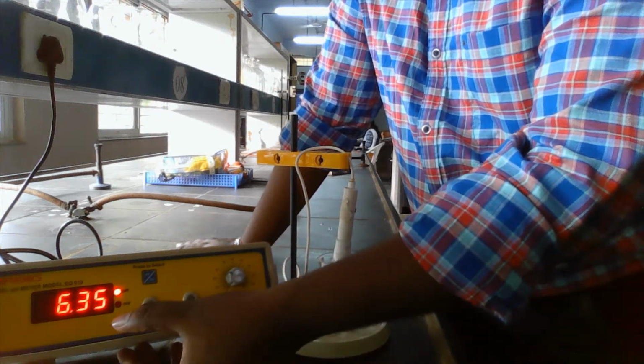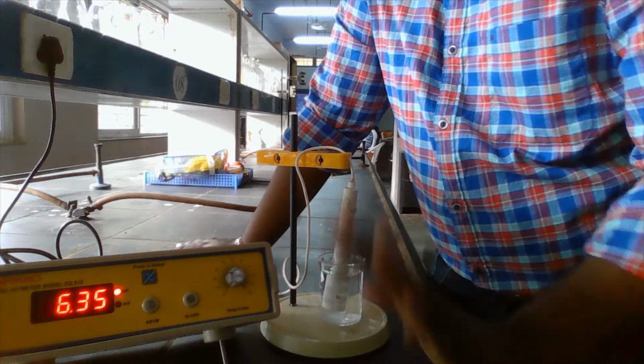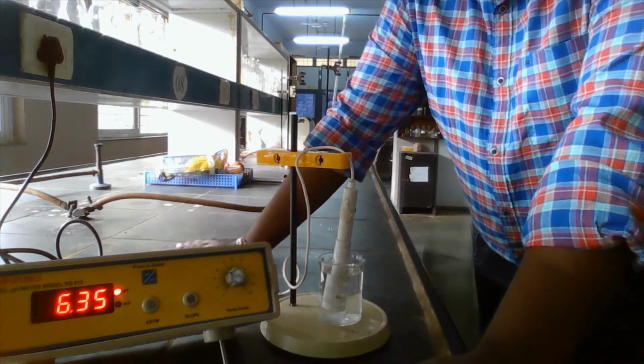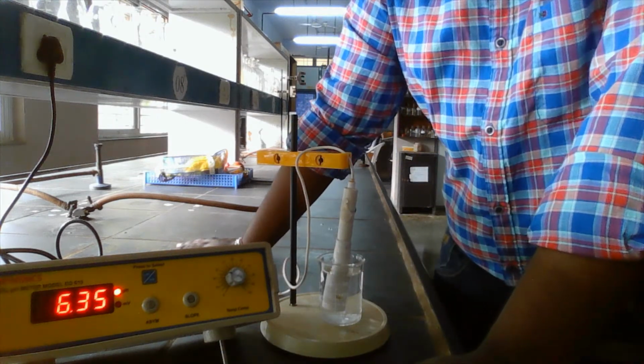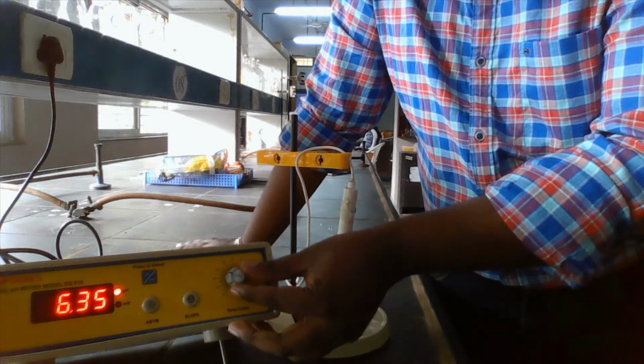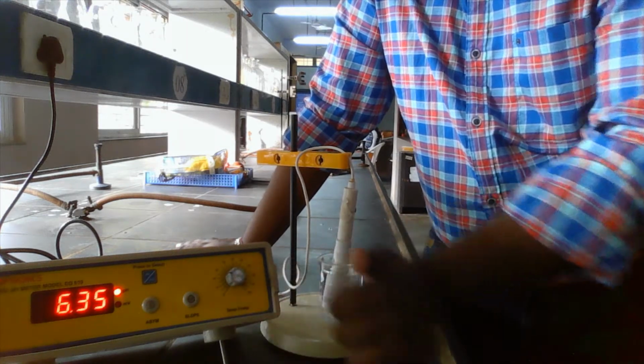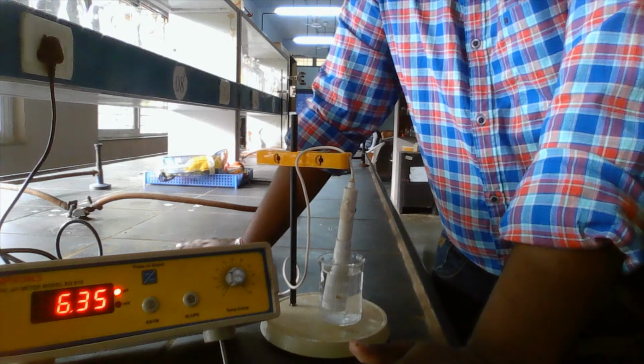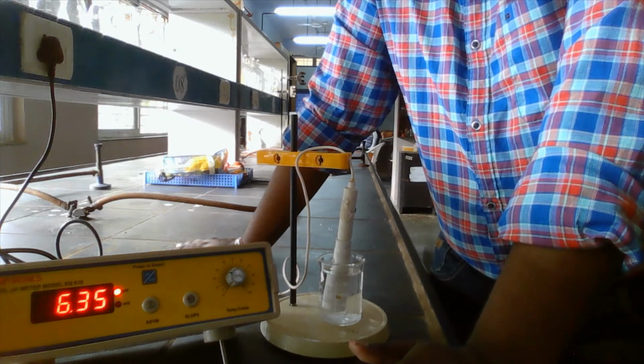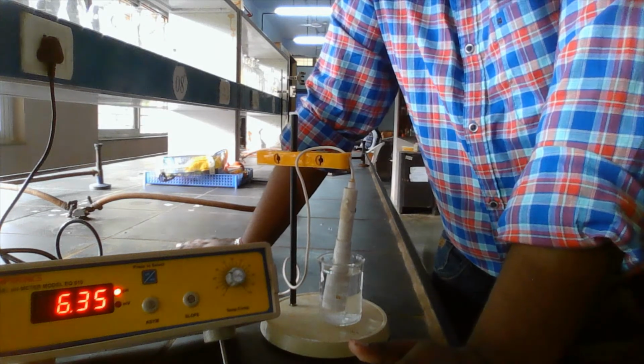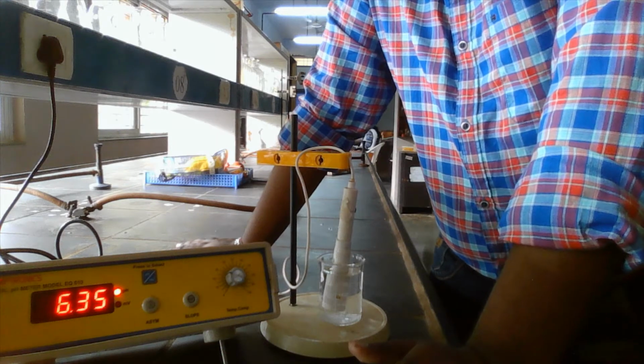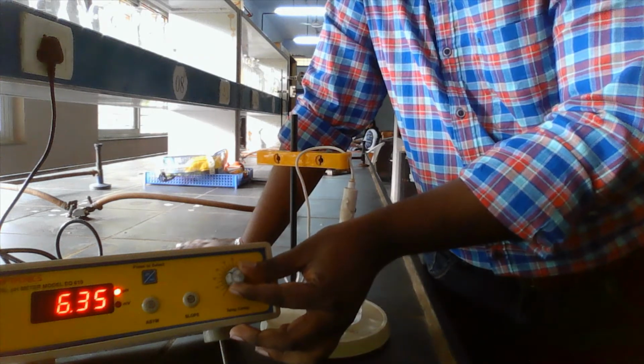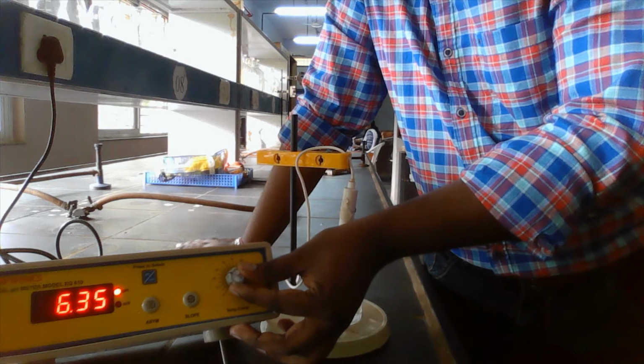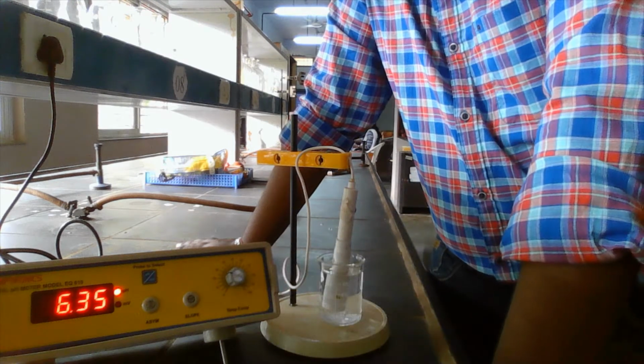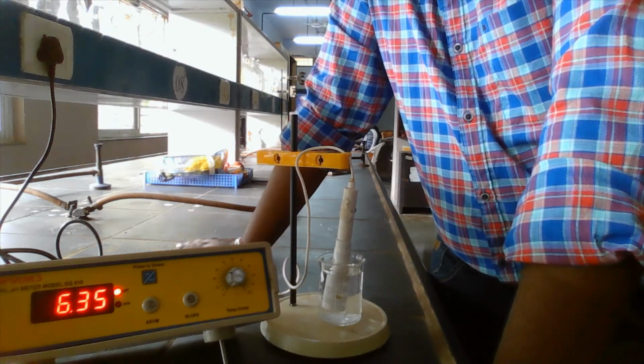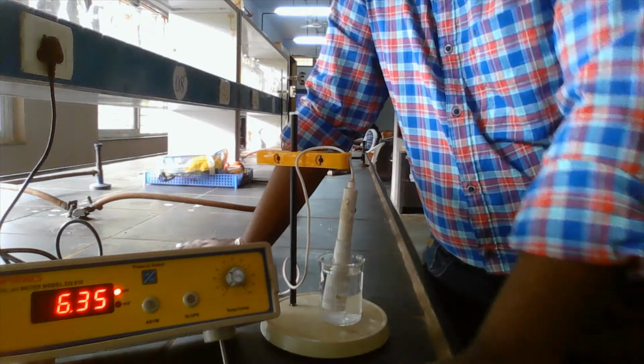And this instrument does not determine only pH, millivoltage can also be determined with the help of this instrument. Here there is a temperature compensator knob, and in this case it means an automatic electrode temperature sensor is not there in this instrument. Hence with this temperature knob we will adjust the pH measurement to the room temperature, and we will measure the corresponding pH. This is the instrument which is available in the laboratory.